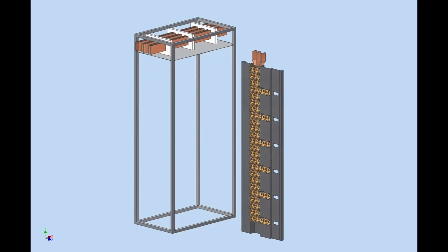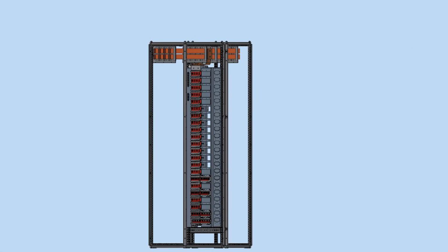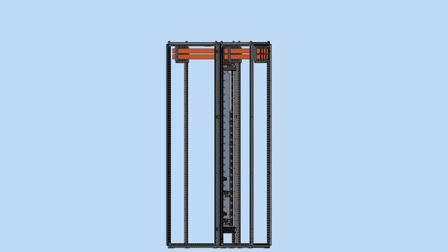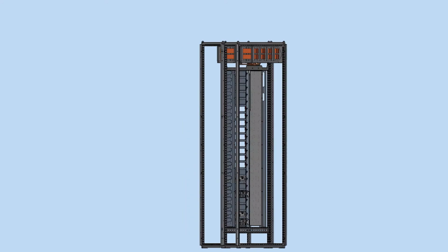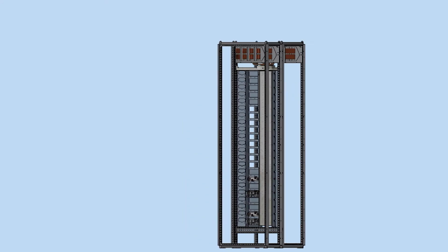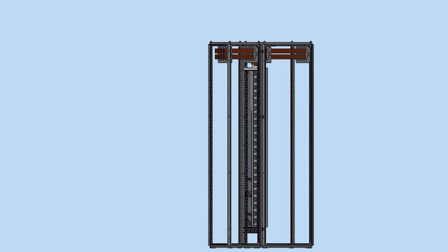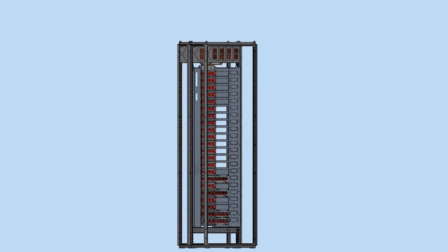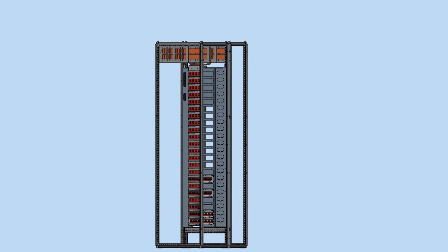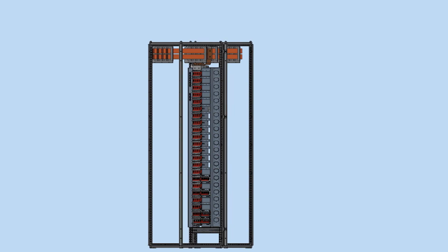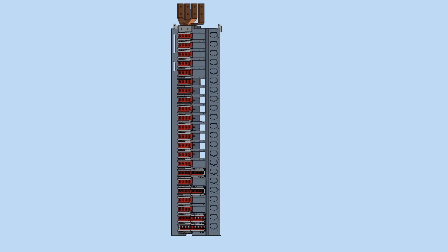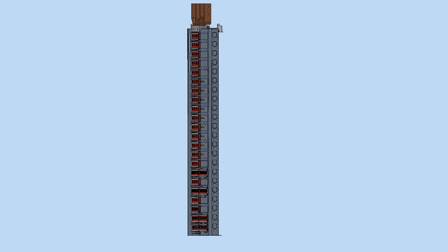The EST wall is of high importance and is responsible to put the Econ SI elements in the right position and strictly in line. The EST wall, energy and signal transfer wall, has to be installed and aligned in such a way that the cable module and busbar module are mounted absolutely in line. Note that compared to competitive systems, the VBB is located at the side and not anymore at the back. This side wall, called EST wall, is the absolute central part and makes the switchboards based on the technology so flexible.